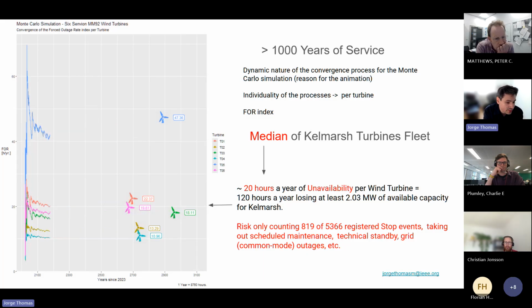You have intervals there, and you can see here, for instance, I just wrote 20 hours around here, 20 hours a year of unavailability per wind turbine, which means 120 hours a year losing at least 2.03 megawatts of available capacity for Kelmarsh. That's the interpretation there.